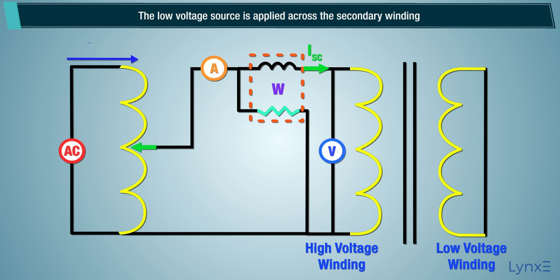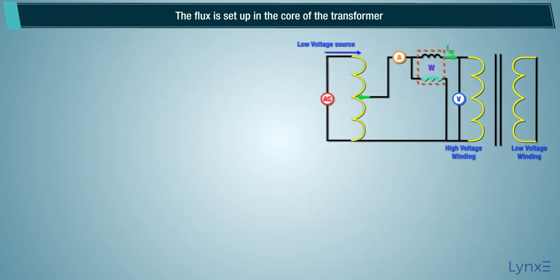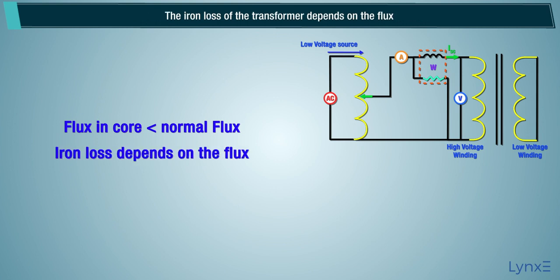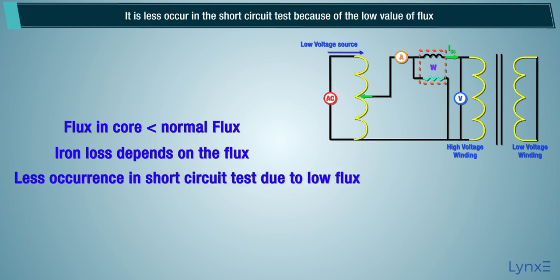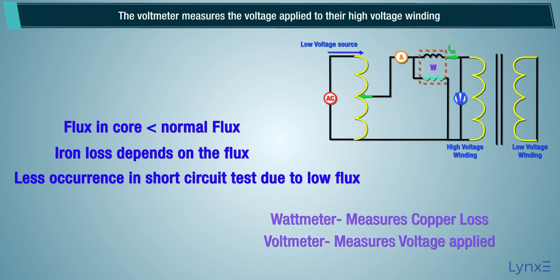The low voltage source is applied across the secondary winding, which is approximately 5 to 10% of the normal rated voltage. The flux is set up in the core of the transformer. The magnitude of the flux is small as compared to the normal flux. The iron loss of the transformer depends on the flux; it is less in the short circuit test because of the low value of flux. The reading of the wattmeter only determines the copper loss occurring in the windings. The voltmeter measures the voltage applied to the high voltage winding.